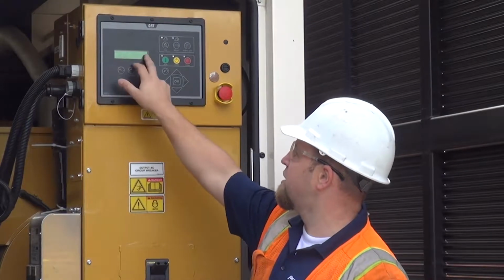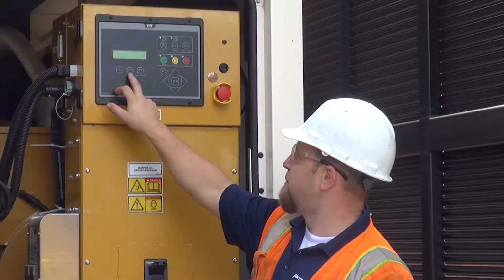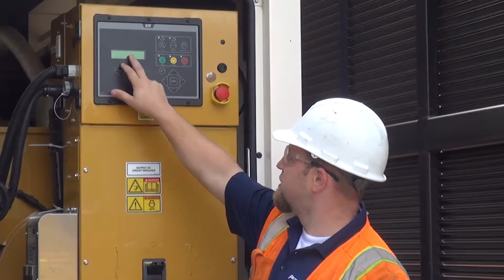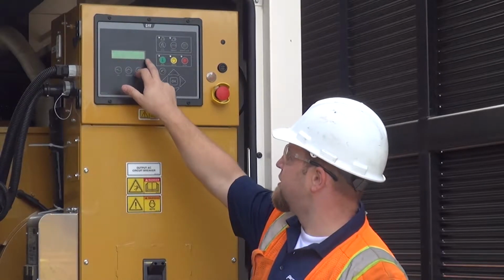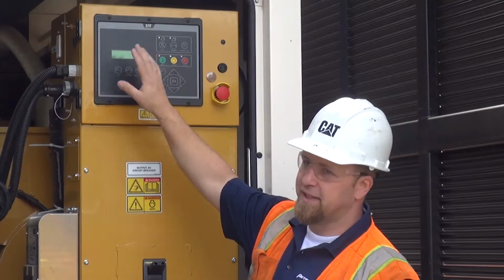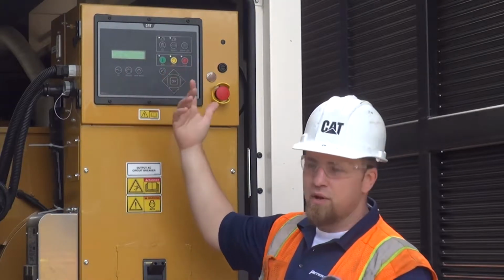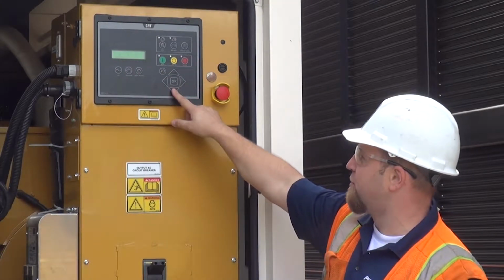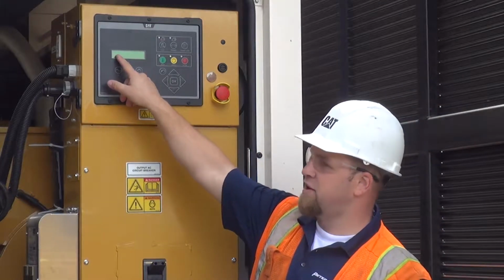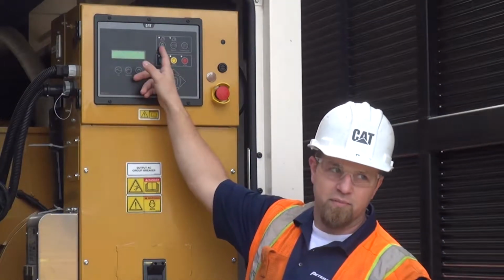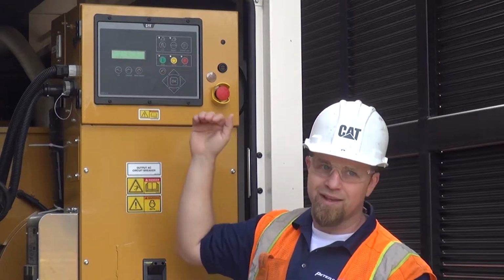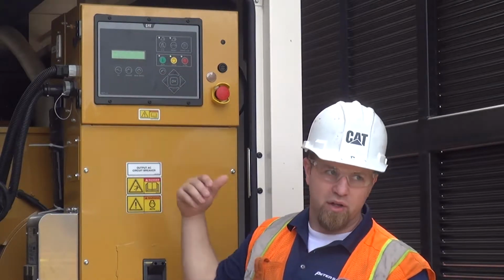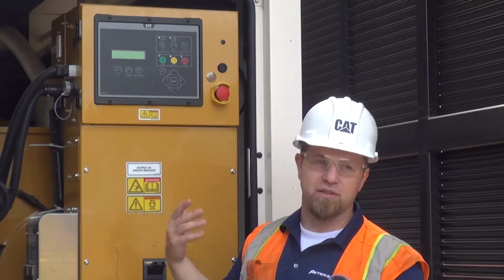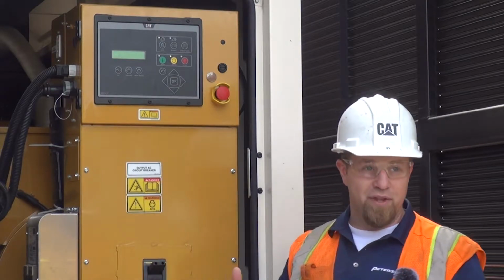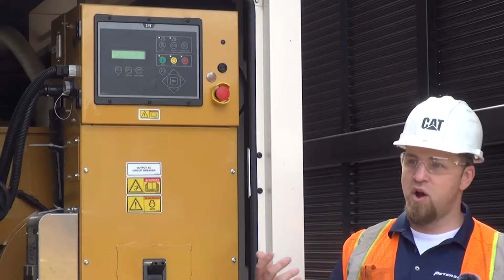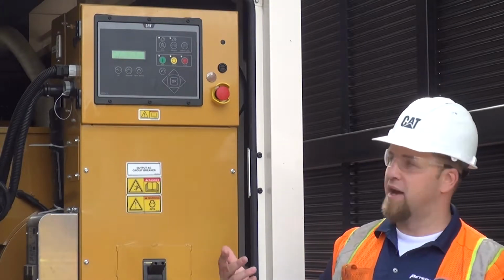So AC right here, this main screen is just like your engine main screen -- you've got voltage, amps, hertz, kilowatts, and percentage. This is the main screen you'll really use, but it's worth scrolling down, because you'll see line-to-line readings on each phase. If you notice one leg is crazy high or low, that's a red flag, especially while still under warranty or while everyone's still on site. The more you check that, the better.